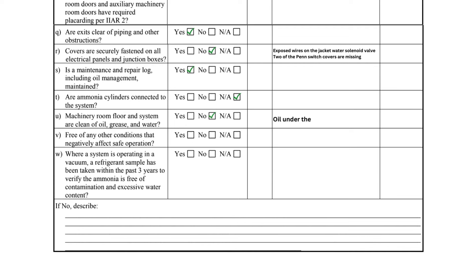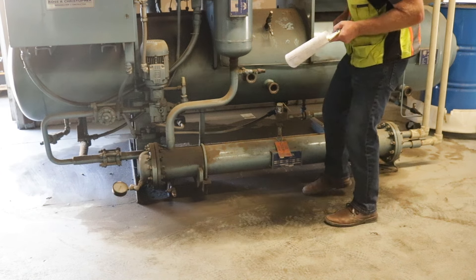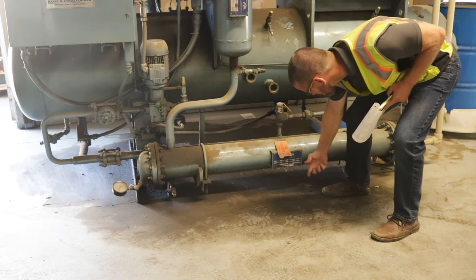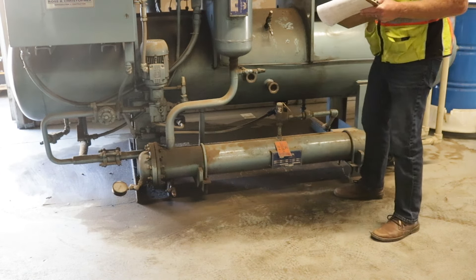Item U asks if the machinery room floor and system are clean of oil, grease, and water. This screw compressor has noticeable oil on the ground that must be cleaned up.